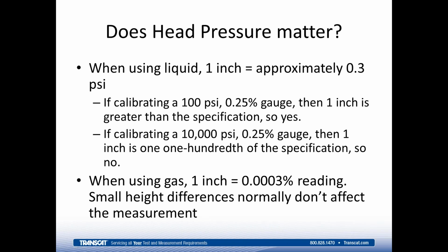When using gas, the head correction is still physically there. There's going to be a difference in reading, but the density of gas is much smaller. The other aspect with gas is that the density of the gas is not thought of as a constant. With a liquid, we think of it as being non-compressible, so that the density is the same no matter what the pressure is. With gas, that is not true. It compresses. So as we go higher in pressure, we have a higher density. So a good approximation for most pressures and most gas media is about 3 parts per million, or 0.0003% of reading. So if the calibration that we're doing is once again on that 0.25% or 1/4% gauge, 1 inch of head height has more or less no bearing on our calibration.